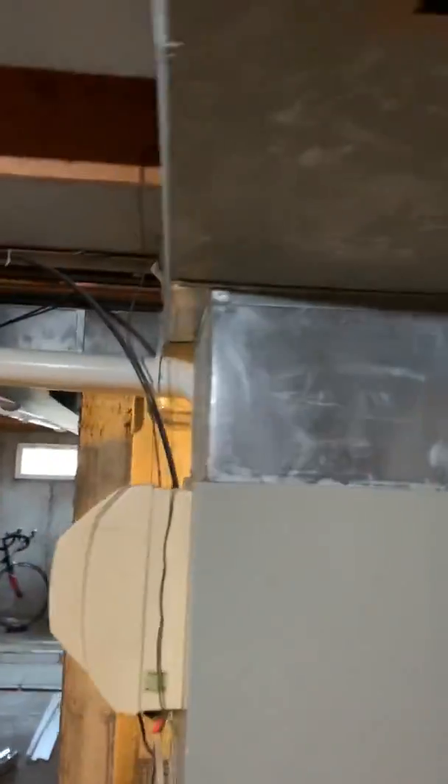The return is actually the right size. The filter cabinet is a 7-inch filter cabinet. We've been putting our 5-inch filter in here the last couple years. He's had maintenance with us, so we've got our filter upgrade in there.